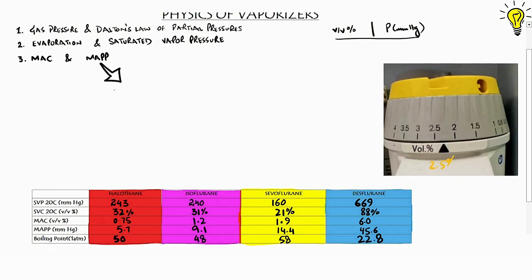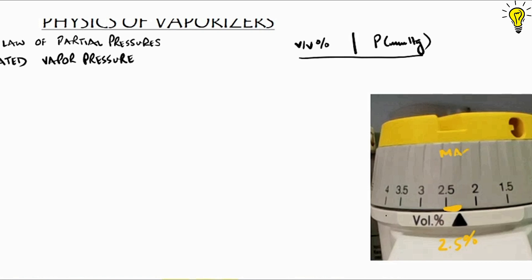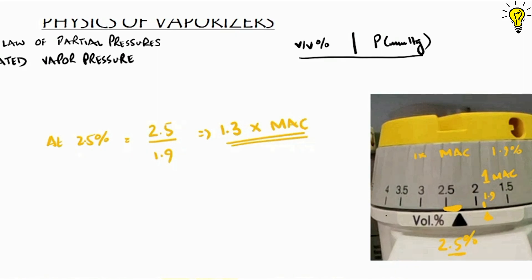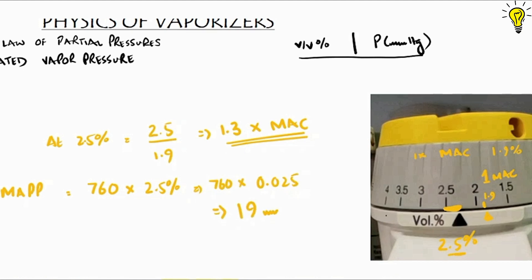Here in the picture, I have set the vaporizer dial at 2.5%. In terms of MAC value, divide 2.5% by 1.9% for sevoflurane — and this 1 MAC value for other gases is different, as you can see in the table; for isoflurane it is 1.2%. So 2.5% ÷ 1.9% = 1.3 MAC. 1 MAC prevents movement in 50% of patients; 1.3 MAC prevents it in 95%. In terms of minimum alveolar partial pressure at sea level: 760 × 2.5% = around 19 mmHg is the partial pressure of sevoflurane in the alveolus at this vaporizer setting.